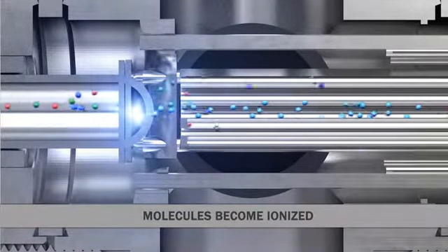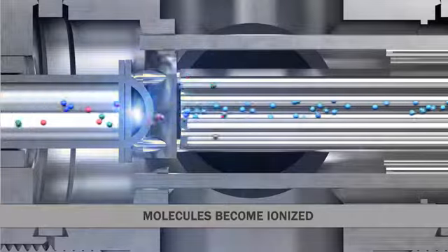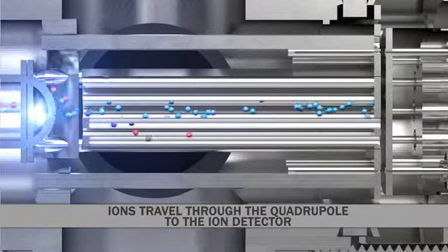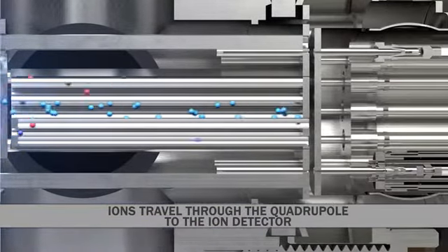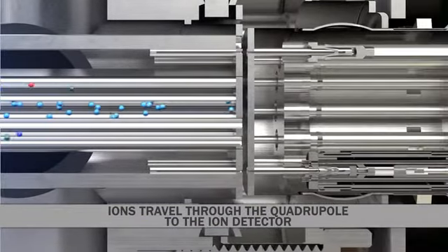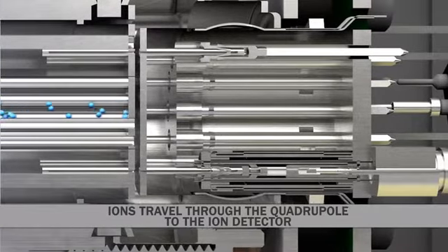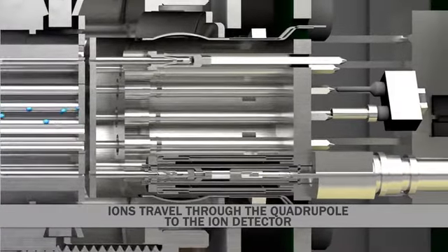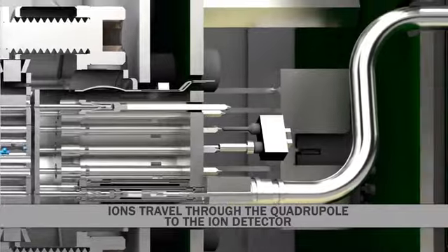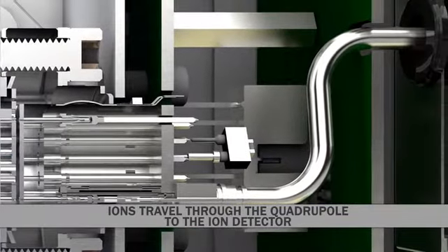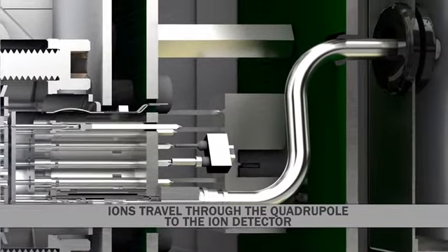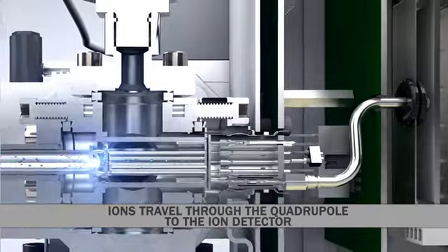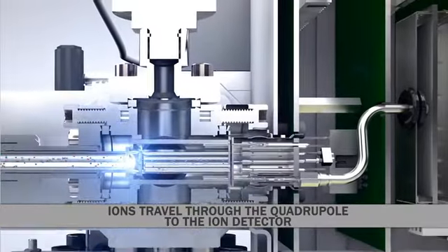These positively charged ions then travel through AMS's quadrupole mass filter, which separates the ions according to their mass-to-charge ratio. The final element in the AMS is a Faraday-Cup ion detector, which records and quantifies the electrically charged ions.